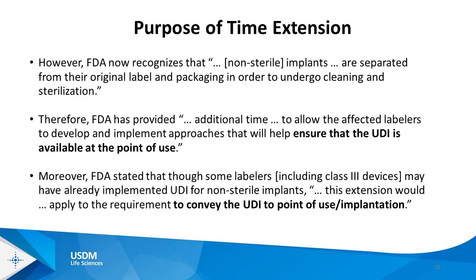So we now have significantly lost our traceability of that individual implant as it moves from its original packaging, where it was UDI compliant, into a set, into a tray or caddy, and into sterilization, and finally into an operating room. So we've now lost that connection. And this time extension has been granted to allow labelers, device manufacturers, to find a way of making sure that the UDI is available at the point of use.